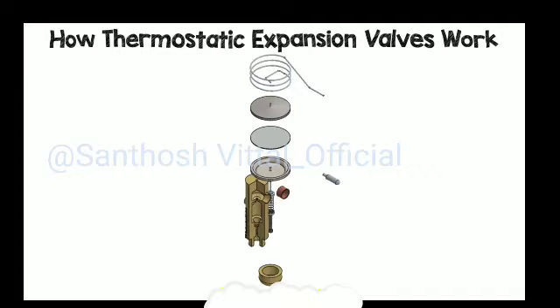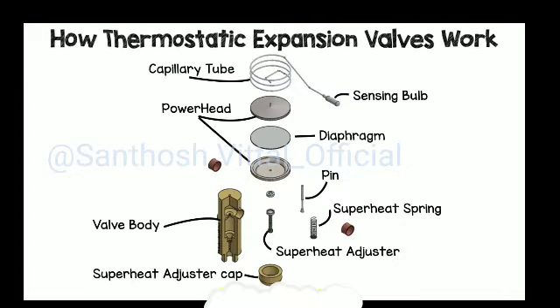So let's just look at the main components inside the thermostatic expansion valve, and then we'll have a look at how the expansion valve works and why. If we pull apart a thermostatic expansion valve, then we're going to see the following main components. The valve body, which holds the components and has an orifice inside to control the flow of refrigerant. Then we have the diaphragm, which is a strong, thin, flexible material, typically metal, which flexes to apply pressure. Then we have the needle or pin and seat. This moves up and down to restrict the refrigerant's flow path. The spring, which counteracts the force of the needle. And we've also got the sensing bulb and the capillary line, which causes the valve to open or close.